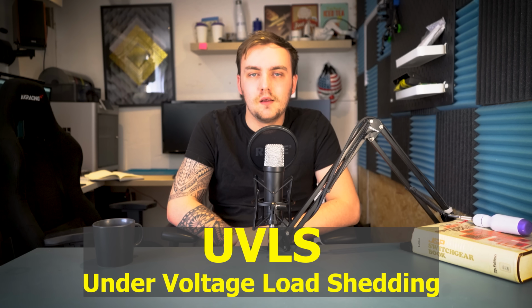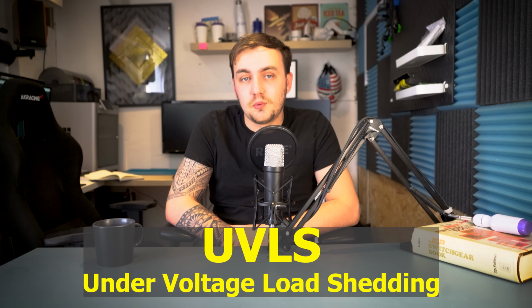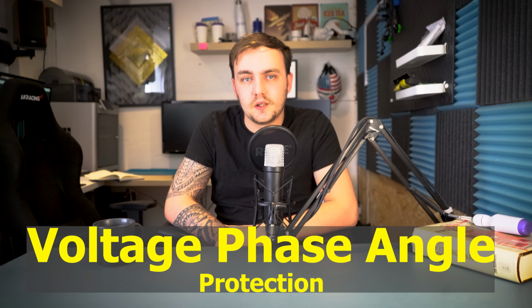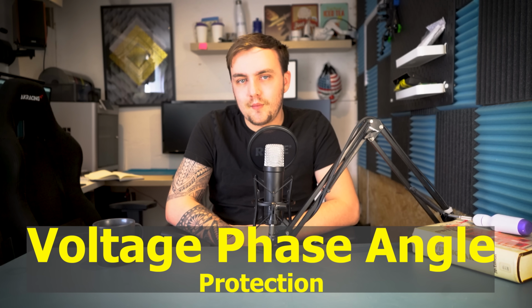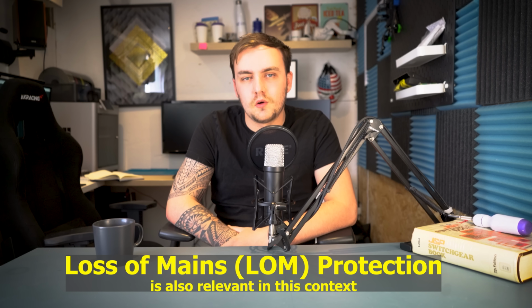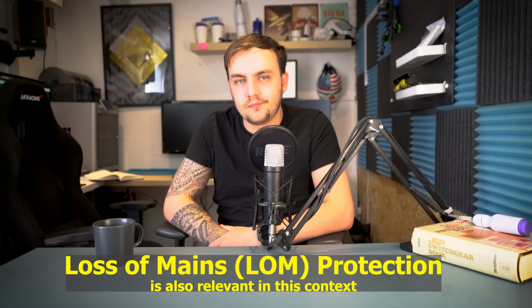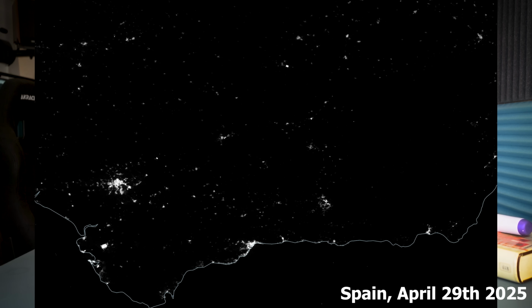Some systems also include under voltage load shedding, or UVLS, as well as voltage phase angle protection, but in the UK, frequency and RoCoF are the main drivers for protection actions in a large-scale disturbance. What happened in 2019 was a partial failure where the system protections worked.